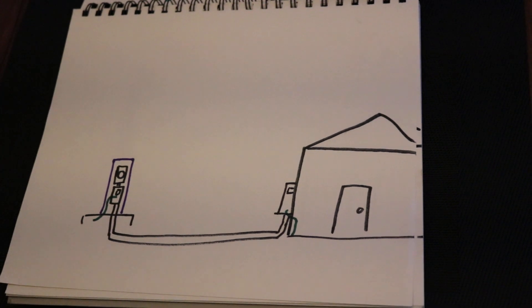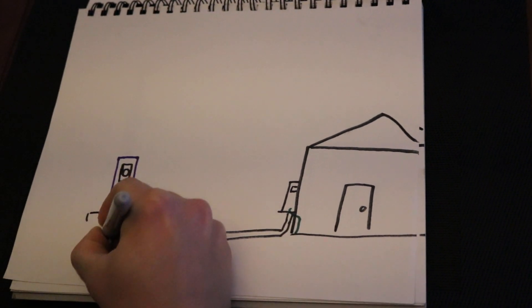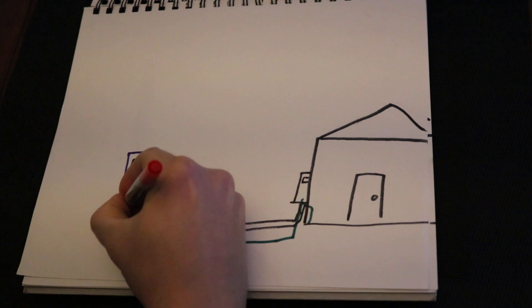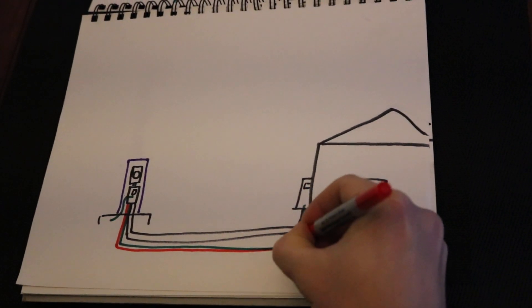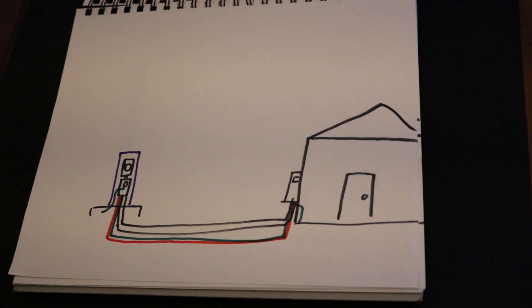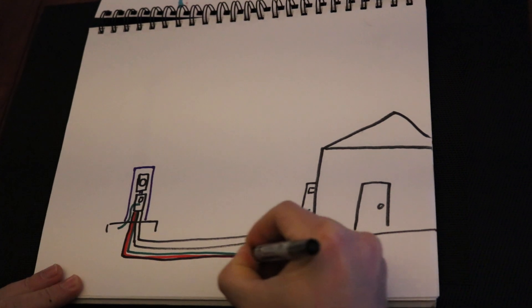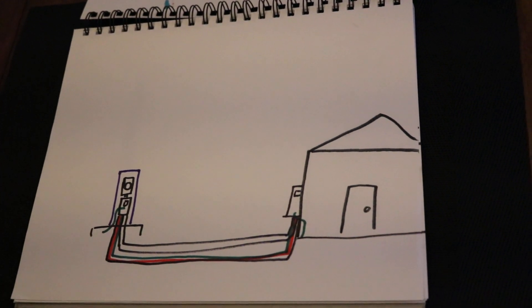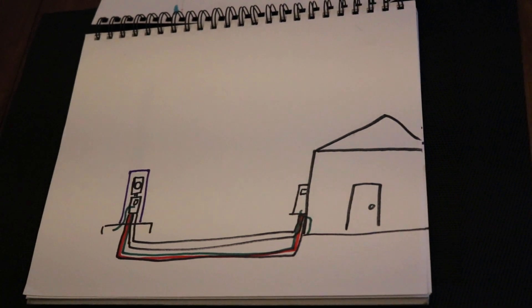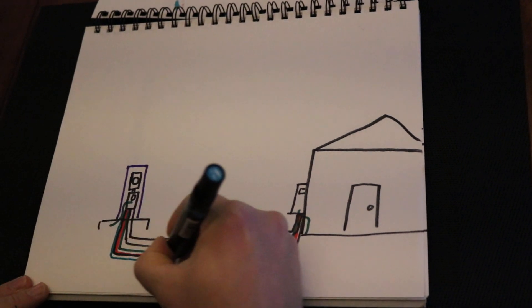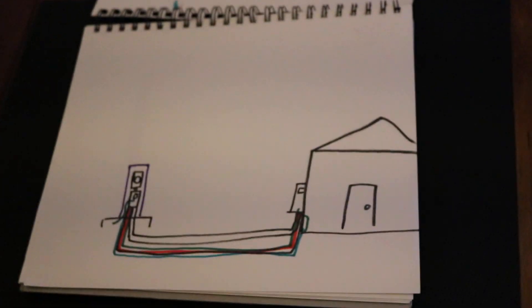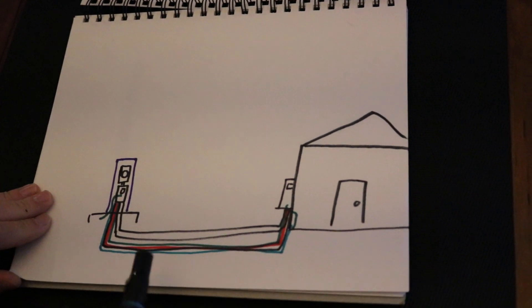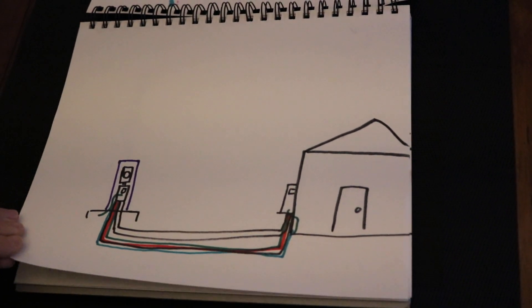This is where your ground and neutral actually bond, at that first disconnect. This is the main breaker disconnect. And then in this conduit you should have a ground wire, your A and B phase, and your neutral which is white. Again, we're using this aqua pen, it's hard to see white on white. So you have four wires going from your pedestal to your panel over here. And I think we covered that pretty well.